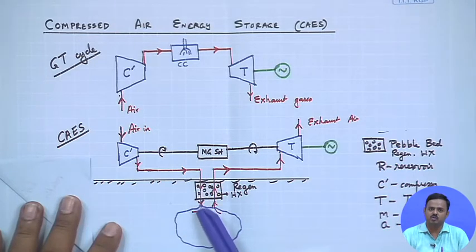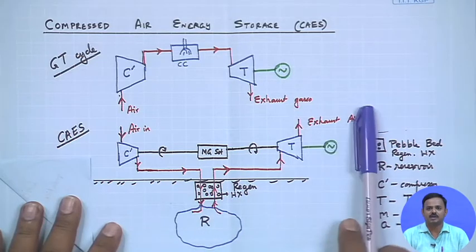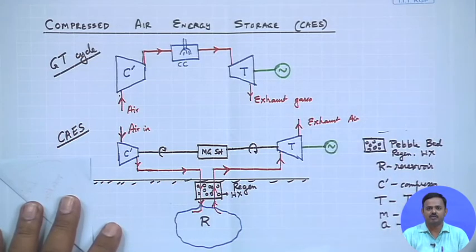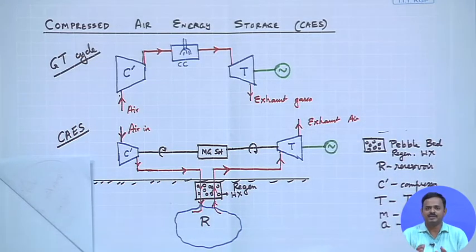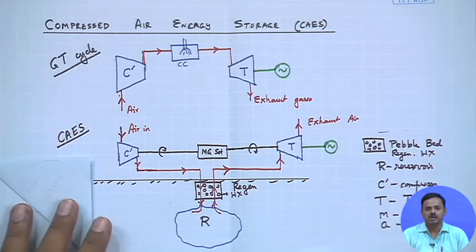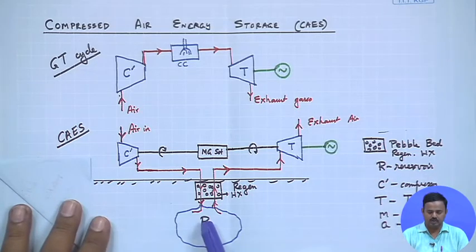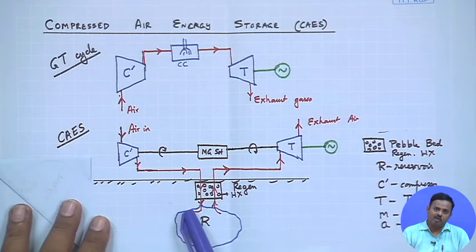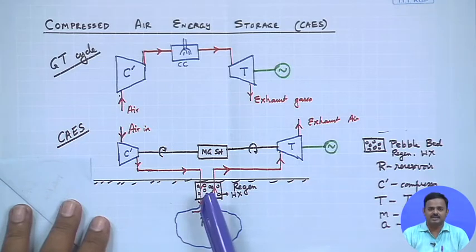Before storing the compressed air in the reservoir, we want to cool it down, because on compression its temperature rises. Cooling it to a lower temperature means the volume it will occupy will be even lesser, so the volume of the reservoir required to store the compressed air is going to be lower.